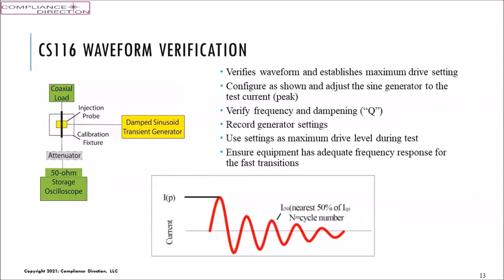We check it at the various frequencies that are assigned for the test, which are 6 standard frequencies, plus the standard talks about using a resonant frequency. Most of the time, we have no idea what that is. We can't control every installation to determine the resonance of the circuit when it's installed. So duplicating that is not realistic. It's a waste of energy because we could check a particular resonance because that's what the room setup did, and the installation is nowhere close to that. So it's not providing any information, but it provides a lot of work.